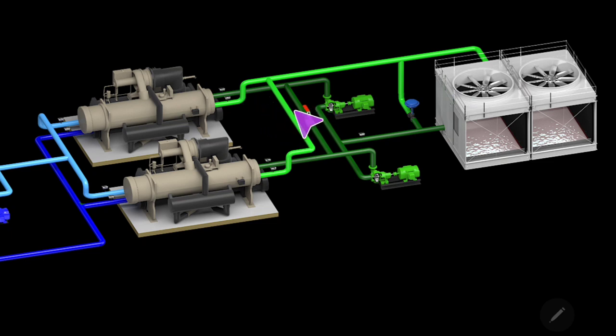I've had a couple of calls recently that I've put out videos on where I discussed that set point. Actually, one of the more recent videos where the call was for a chiller surging, and while I was there I ended up having the electrical main for the whole building trip. The surge for that call was actually due to the condenser water temperature and the chill water set point combined. So in this video let's discuss what are good set points, what are things you want to stay away from, and just my experience and recommendations on the topic.